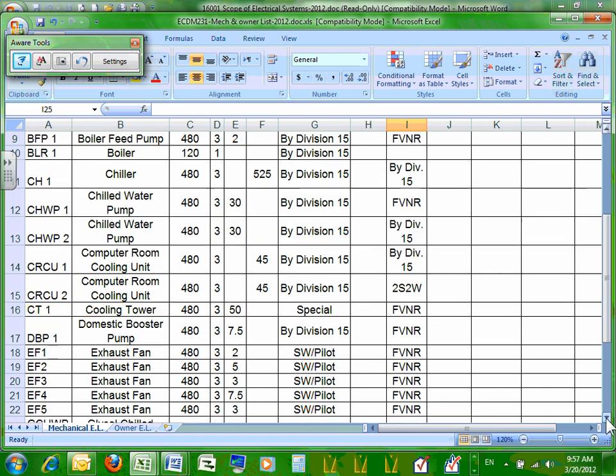One point just flashed in my mind on that little sketch I had: keep in mind, if one PDU goes down, all of that load goes to the other PDU. So each PDU has to be sized to handle 100% of the load. The same thing goes for my UPSs. If a UPS fails, all of that load is instantly on the other UPS. It doesn't skip a beat because both UPSs are feeding and splitting the load. If the other UPS goes down, the load on my surviving UPS doubles right now. Nothing switches, nothing transfers, because they're both serving the same load, and if this one drops off, this one doubles. So you have to size the UPSs and the PDUs to handle the total load.